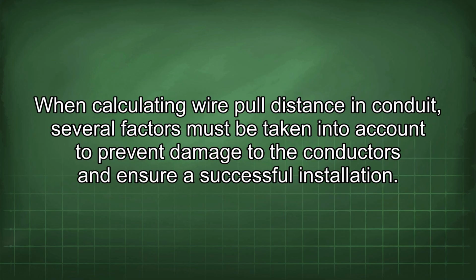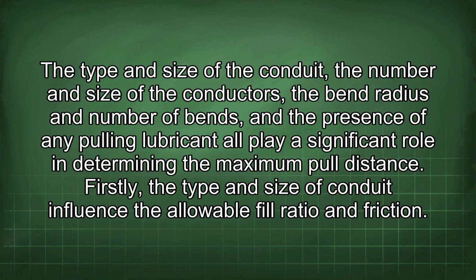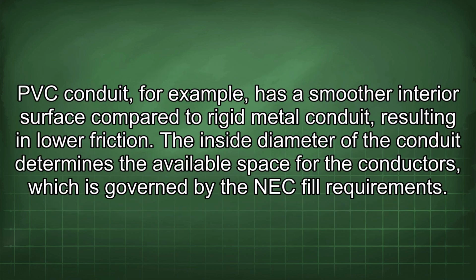When calculating wire pull distance in conduit, several factors must be taken into account to prevent damage to the conductors and ensure a successful installation. The type and size of the conduit, the number and size of the conductors, the bend radius and number of bends, and the presence of any pulling lubricant all play a significant role in determining the maximum pull distance. Firstly, the type and size of conduit influence the allowable fill ratio and friction. PVC conduit, for example, has a smoother interior surface compared to rigid metal conduit, resulting in lower friction.